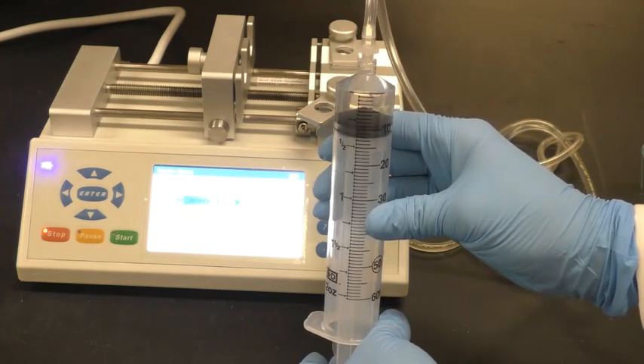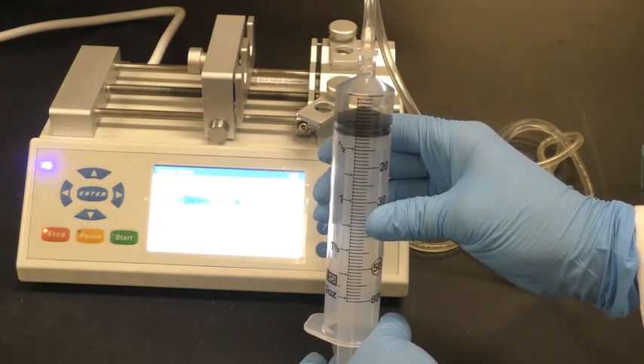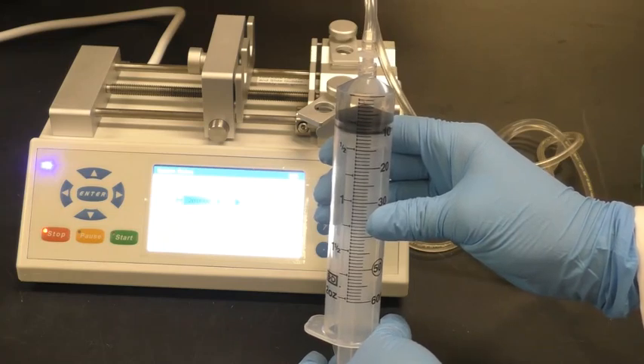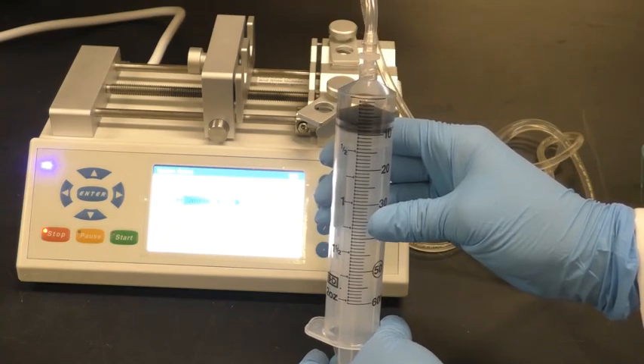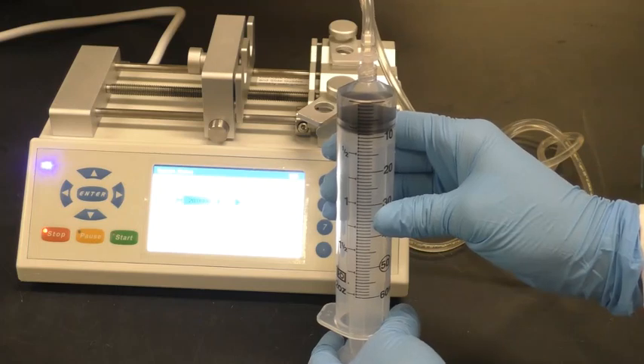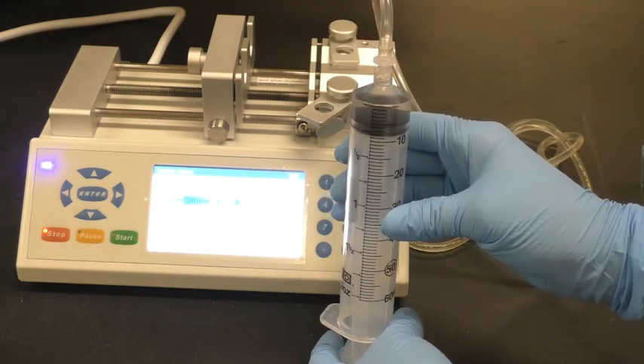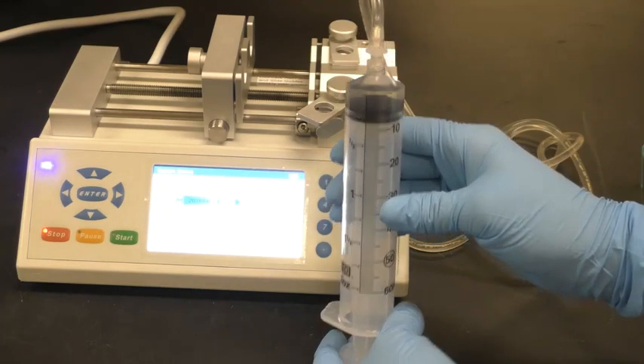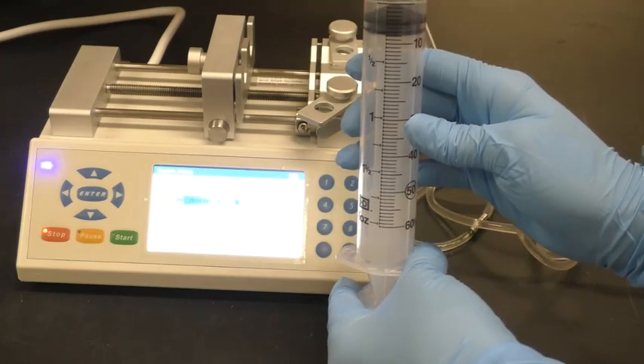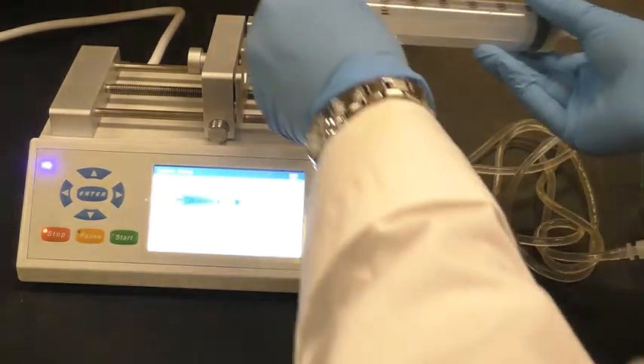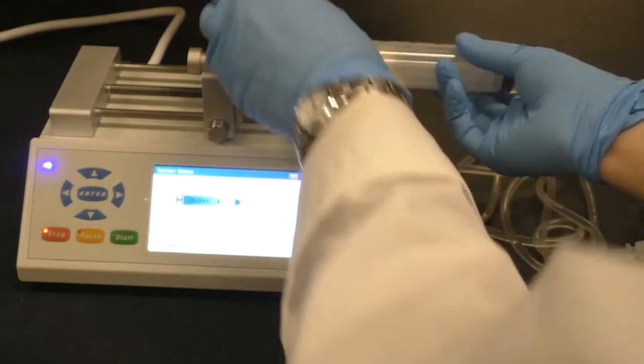If you had to push further than 5 ml to remove all of the bubbles in the tubing, you can then use the syringe pump to withdraw again at a rate of 1 ml per minute until you get 5 ml of blood substitute in the syringe. Once the step is done, you can put the syringe back into the syringe pump and tighten the fittings. Make sure that the syringe pump is very secure. Now you're ready to prep the cell culture portion.